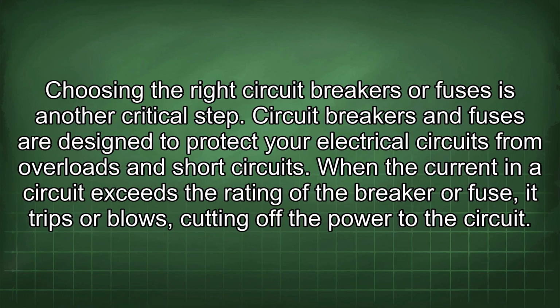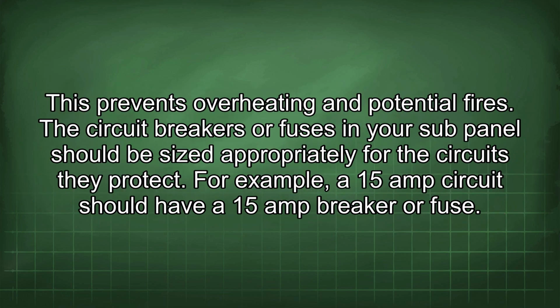Choosing the right circuit breakers or fuses is another critical step. Circuit breakers and fuses are designed to protect your electrical circuits from overloads and short circuits. When the current in a circuit exceeds the rating of the breaker or fuse, it trips or blows, cutting off the power to the circuit. This prevents overheating and potential fires. The circuit breakers or fuses in your sub-panel should be sized appropriately for the circuits they protect. For example, a 15 amp circuit should have a 15 amp breaker or fuse.